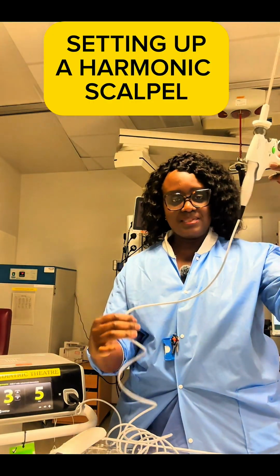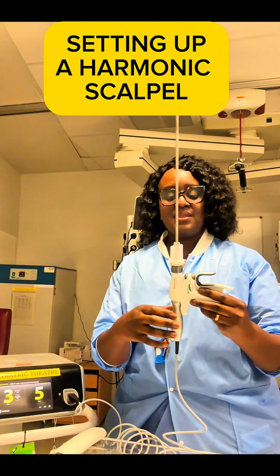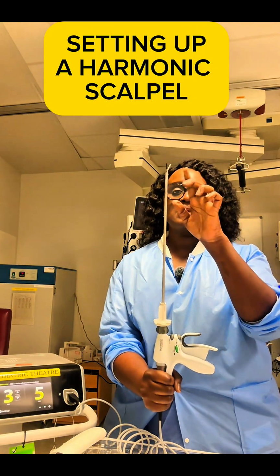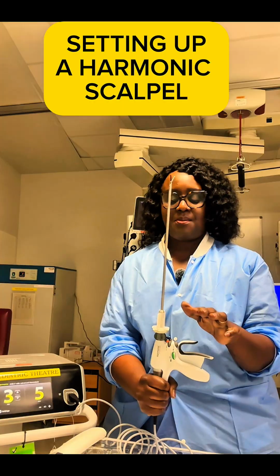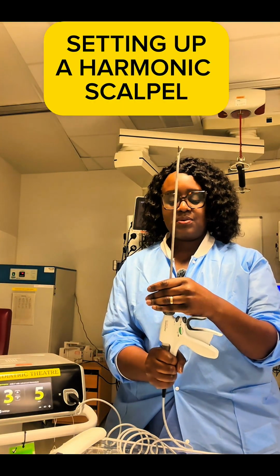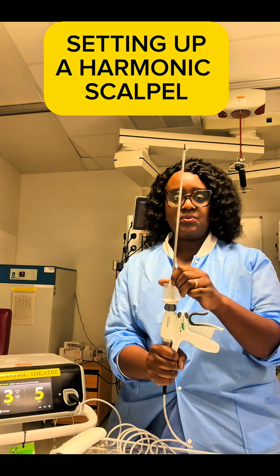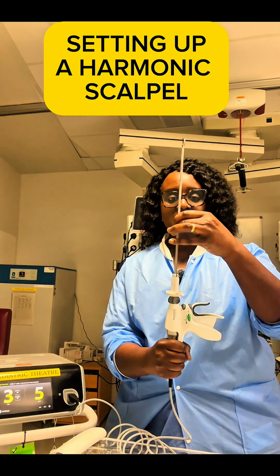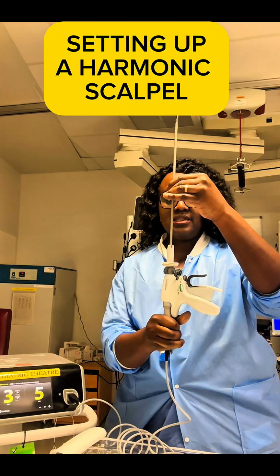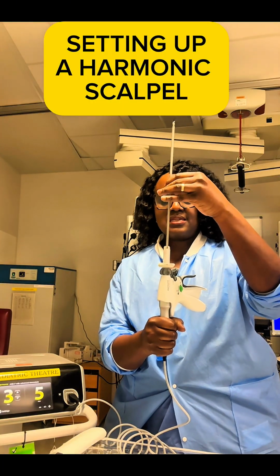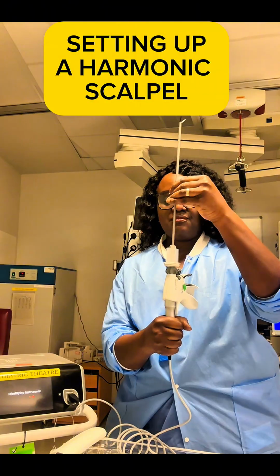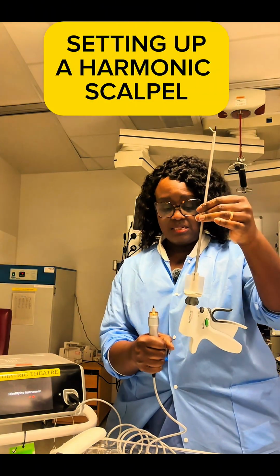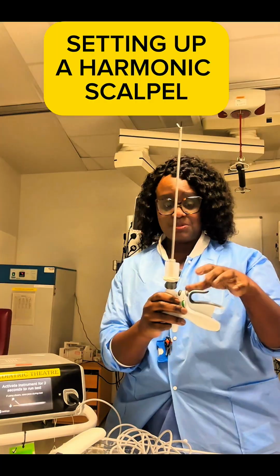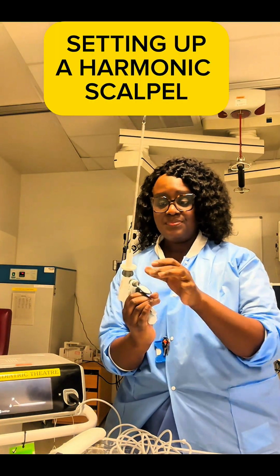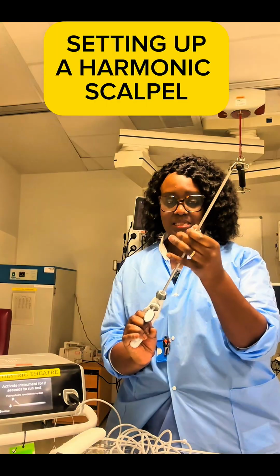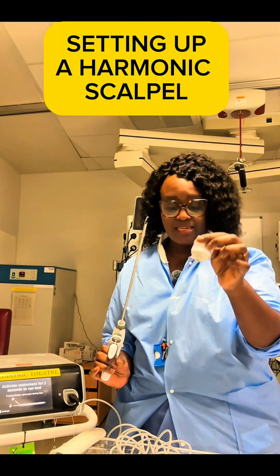After use, remember this is non-disposable. So again, hold there. This is now contaminated. Be careful, treat it as a sharp. And then turn it anti-clockwise. So it unlocks. Then continue with the shaft, unlocking the shaft, holding the handpiece until this comes out by itself. That's out. This is disposable, remember? This is non-disposable. Lock the jaw. Bring the non-disposable piece out because you still need it for the next case.